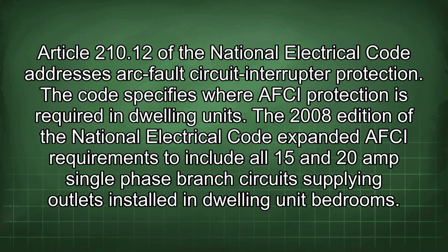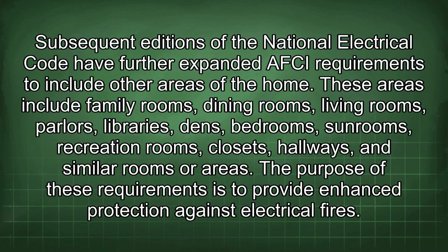The 2008 edition of the National Electrical Code expanded AFCI requirements to include all 15 and 20 amp single-phase branch circuits supplying outlets installed in dwelling unit bedrooms. Subsequent editions of the National Electrical Code have further expanded AFCI requirements to include other areas of the home. These areas include family rooms, dining rooms, living rooms, parlors, libraries, dens, bedrooms, sunrooms, recreation rooms, closets, hallways, and similar rooms or areas. The purpose of these requirements is to provide enhanced protection against electrical fires.